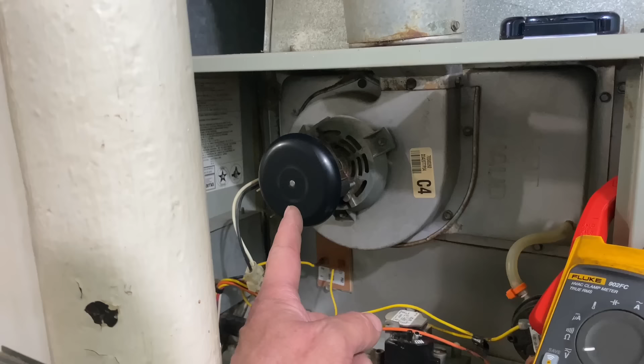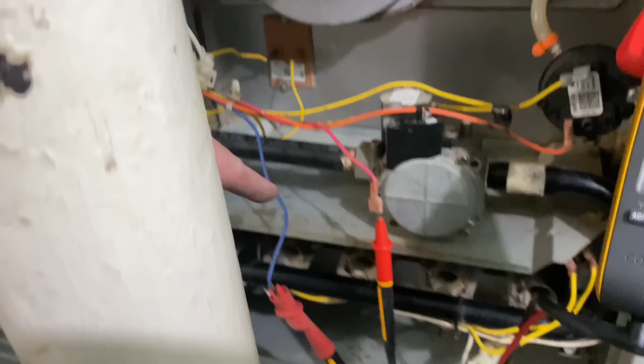And let's confirm. All right, we've got our multimeter set to read volts AC. We have the 2 wires going to the gas valve disconnected, and I have the door switch taped off. Let's turn power on. Click of the relay on the control board. 110 volts is going to our inducer assembly. Once the pressure switch sees that pressure, and the high limit and the 2 rollouts are okay, and our high temperature limit sensor is not open on safety, we'll get 24 volts to the gas valve. Let's wait and see what happens.